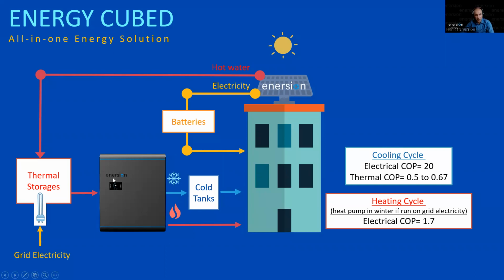One thing about the electrical COP of our chiller: we have an audited report on that, and if anyone is interested, I could share it with you. It's around 20. So for every kilowatt of electricity that goes into this box, we produce around 20 kilowatts of cooling, which is significantly better than a traditional air conditioning system, which is around 3.5. Our thermal COP is between 0.5 and 0.67. In the heating cycle, our electrical COP is around 1.7, meaning if you generate 1 kilowatt of heat in November, we provide around 1.7 times that to the building, because we convert it to a heat pump in the colder months of the year.